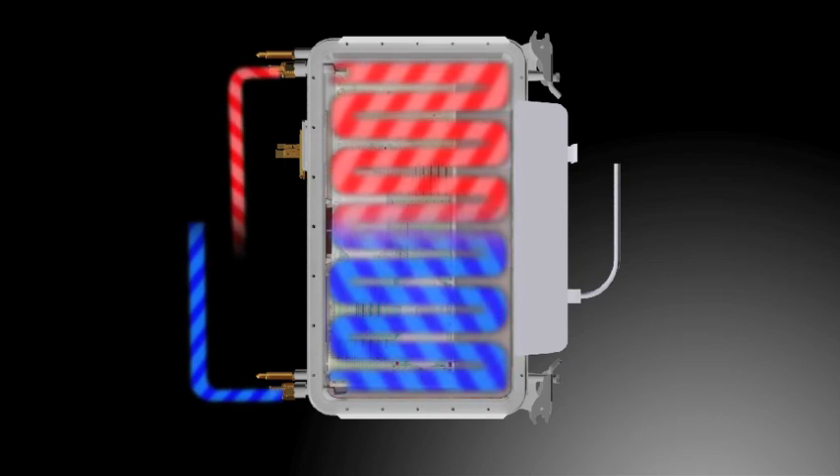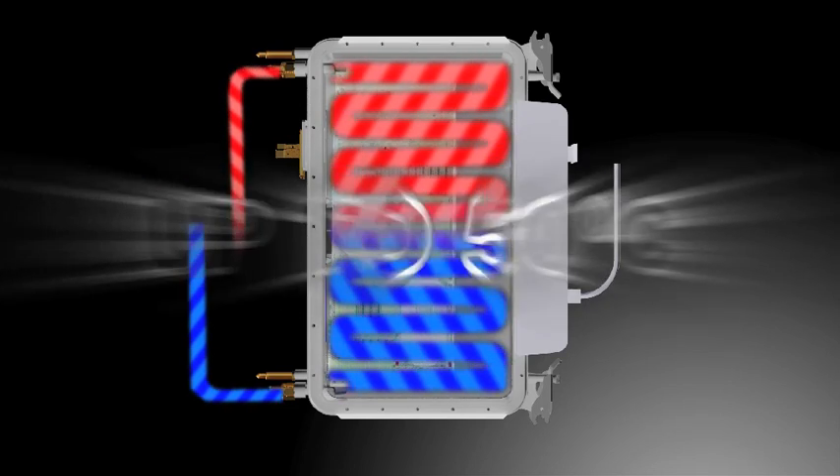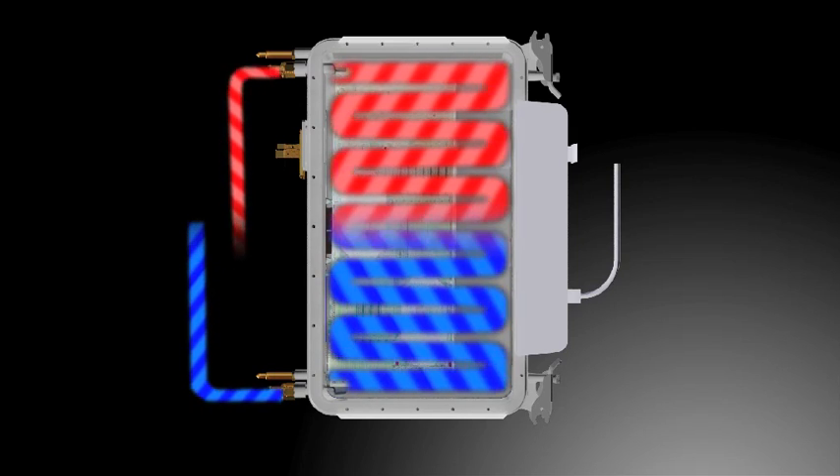Heat is extracted from the Iceotope module by water channels that are cast into the design. The water used doesn't need to be chilled and can actually be up to 50 degrees C and still be effective. This means that even in equatorial regions, the platform will allow for full-time free cooling anywhere. As a by-product, the warm output water can be used in other applications such as building heating.